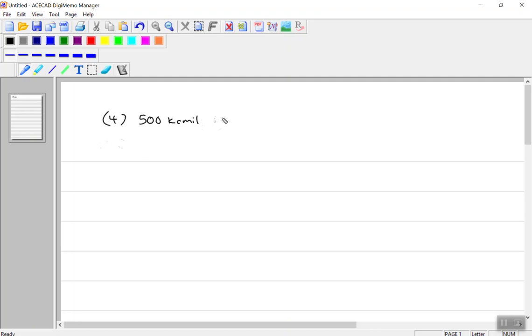and these particular conductors are insulated with THW. Okay, and so that's important, right? The insulation dictates the area of the conductor. They're thicker, thinner, whatever. And then there's also 4 different size and different insulation. This one's a 2-AWG, right? And a different insulation yet. So this one is kind of throwing a little bit of a curveball at us here, right? We've got a different size wire and a different insulation type. So this we've got to double, triple check, make sure we don't make a mistake. Not hard, just slow.